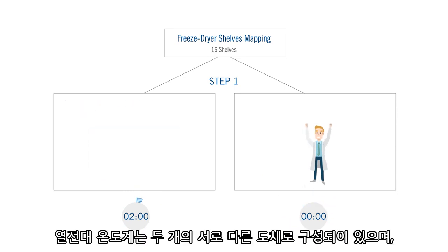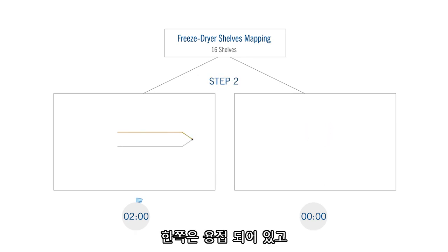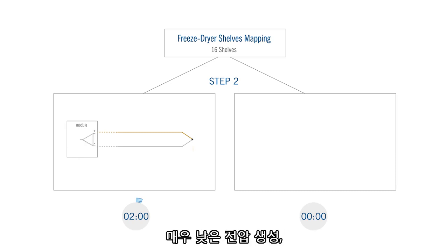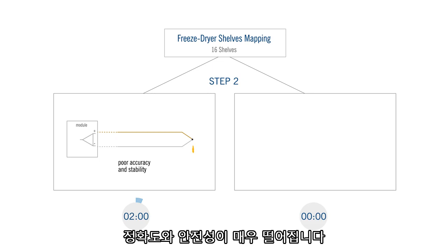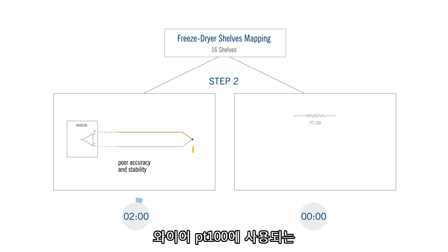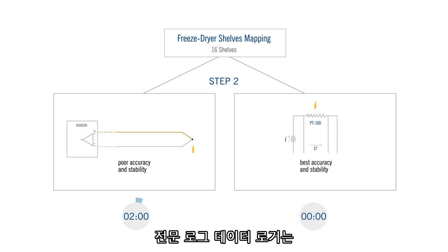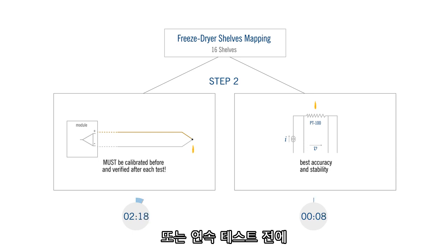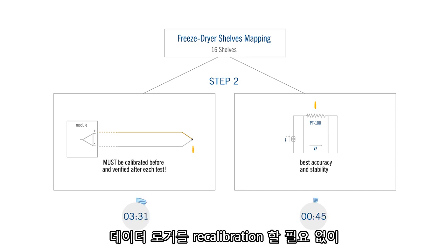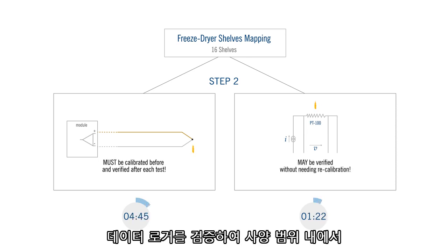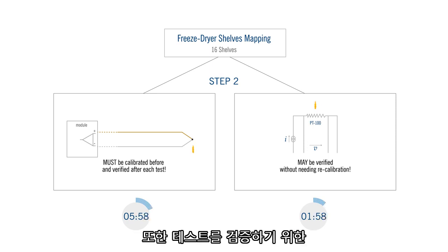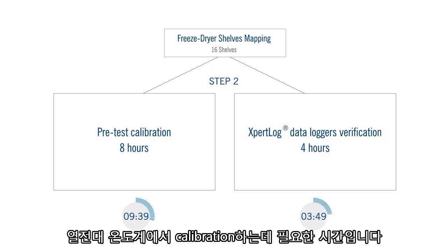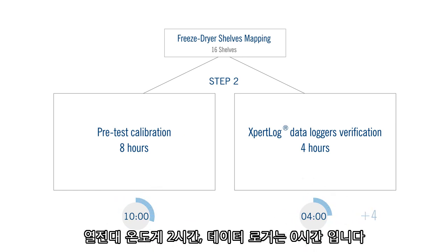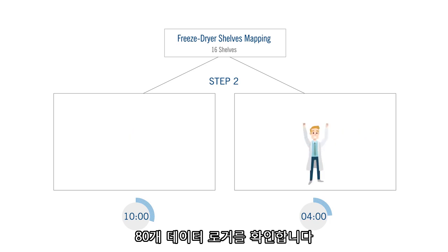Obvious winner, data loggers. The thermocouple is made of 2 different conductors welded on one side and connected to a module on the other side, generating a very low voltage corresponding to the temperature measured, thus very poor accuracy and stability. XpertLog data loggers use 4-wire PT100, which provides state-of-the-art accuracy and stability. As a consequence, the thermocouples must be calibrated before and verified after each test or succession of tests, while the data loggers may be verified to prove they are within specs without needing to recalibrate them. These accuracy measurements before and after the test are a safety feature to validate the test, not to mention to comply with the current regulations for autoclave validations. Time needed to calibrate 80 thermocouples, 8 hours versus 4 hours to verify the 80 data loggers. Again, we have a winner, data loggers.